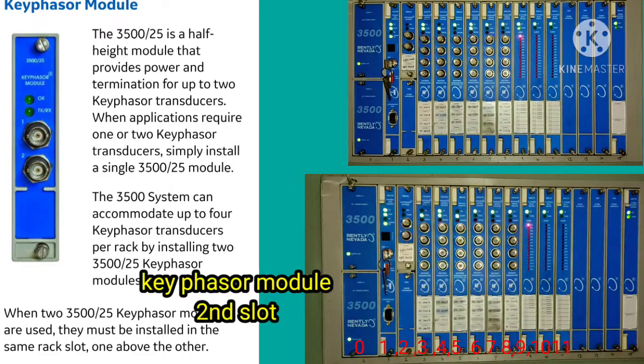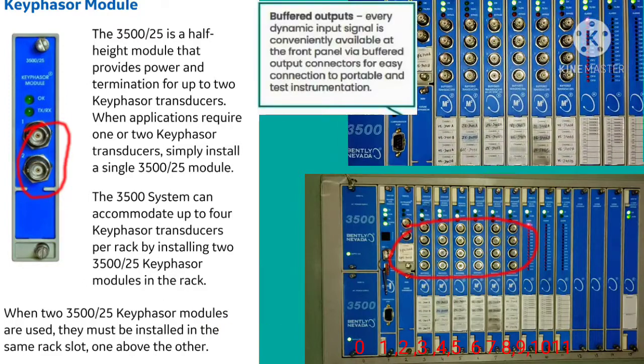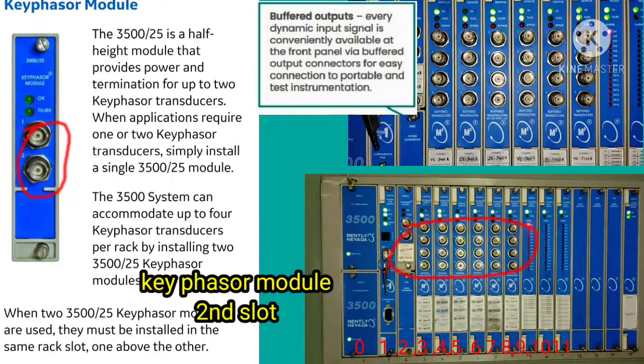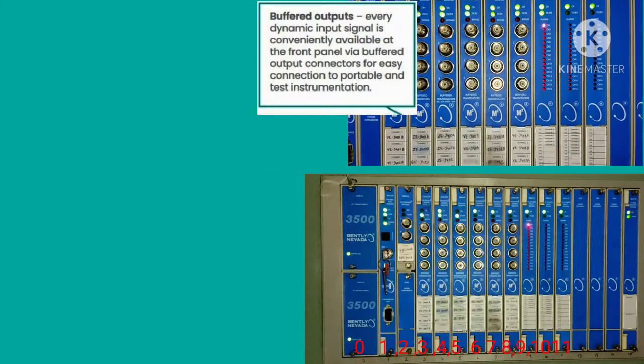The 3500 system can accommodate a maximum of four Keyphasor transducers per rack by installing two modules. When two Keyphasor modules are used, you must install them in the same rack slot, one above another.